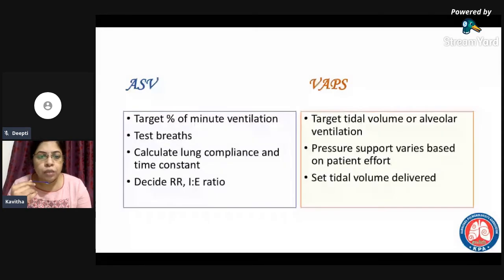you want to achieve. So once you set the patient's ideal body weight and the percentage of minute ventilation, the device will start giving a few test breaths, and based on the test breaths, it will calculate the patient's lung compliance and expiratory time constants. It may feel a bit confusing or a bit difficult to understand, but what you should remember is that there is minute ventilation that is set, and based on the lung compliance and requirements of the patient, the device itself will decide the respiratory rate and inspiratory expiratory ratio and maintain that minute ventilation.